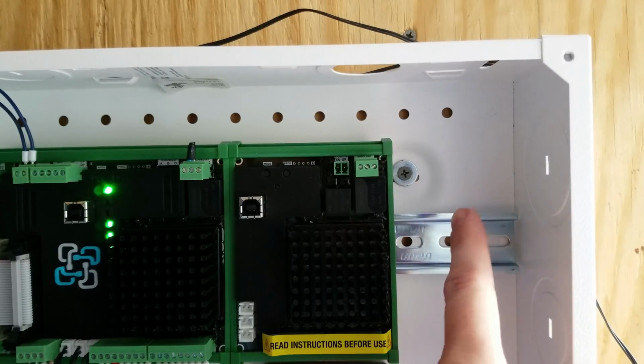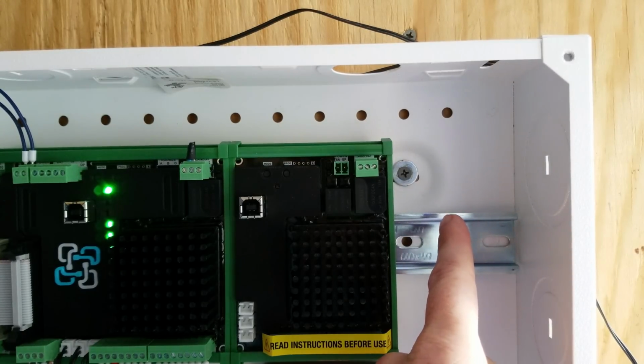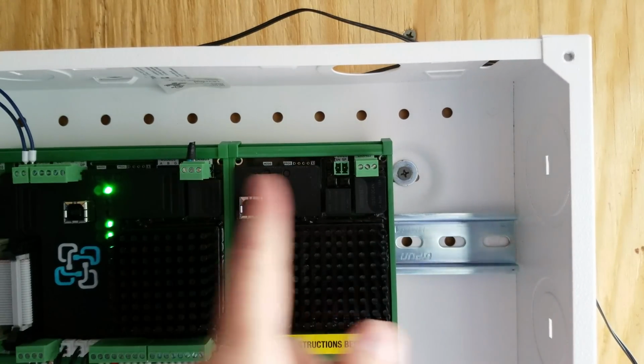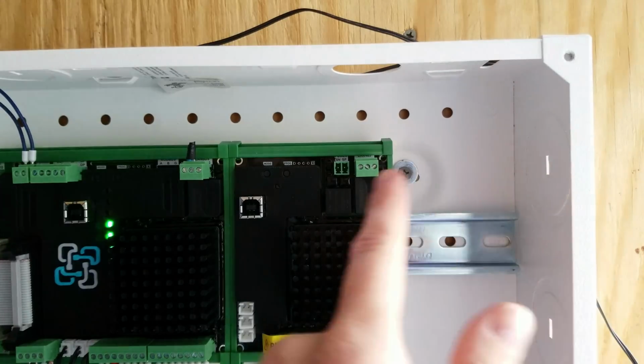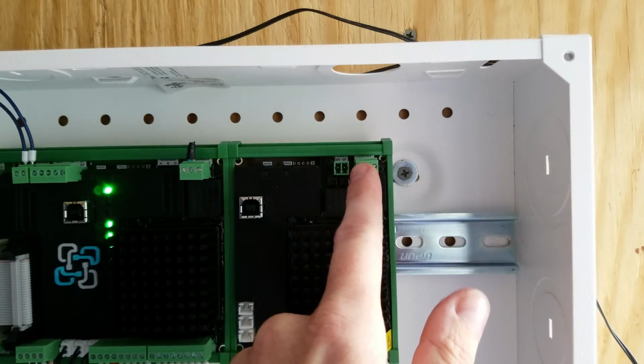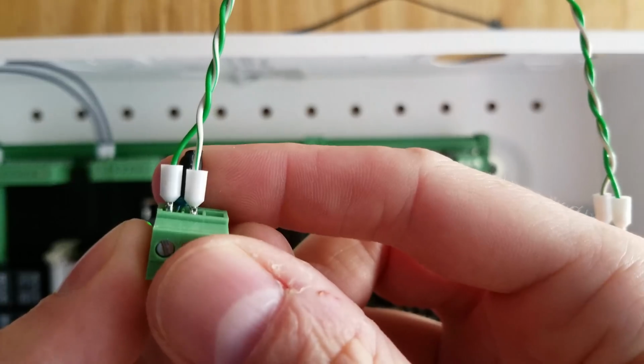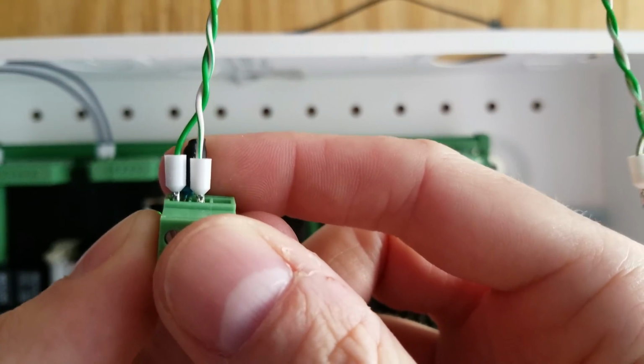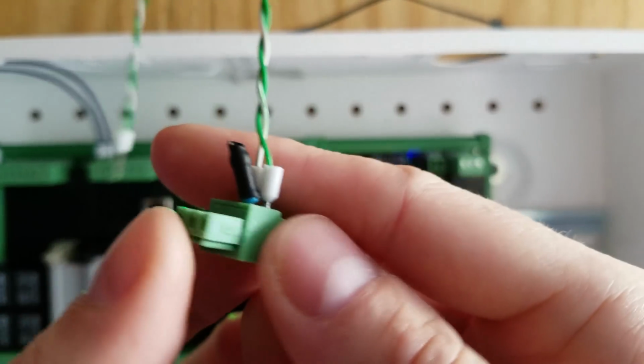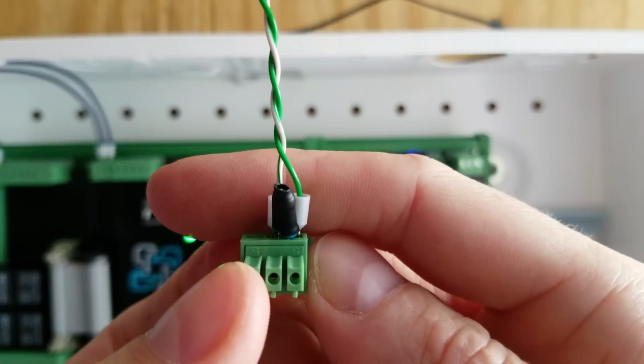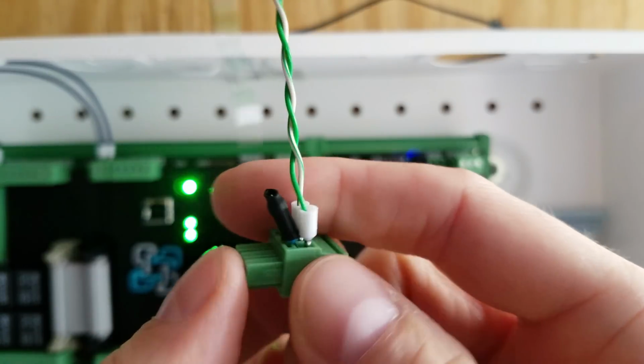Now, if I had a third MM8 over here, I would need a terminating resistor here and a terminating resistor here, but I would not need one on this one since this would be the middle connection in the network chain. All right, so I'm using the green conductor for the high and the striped conductor for the low. And you can see I installed my terminating resistor behind the two connections.